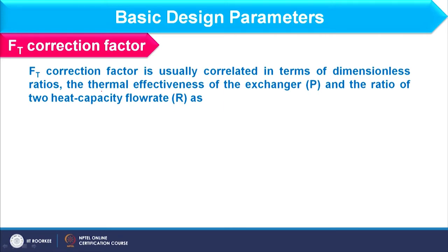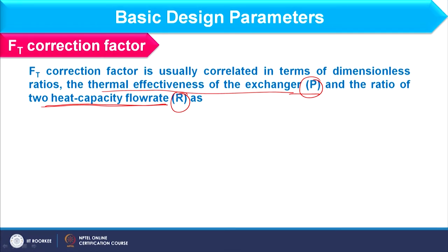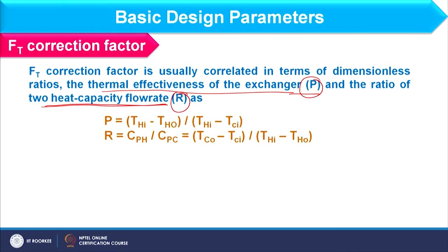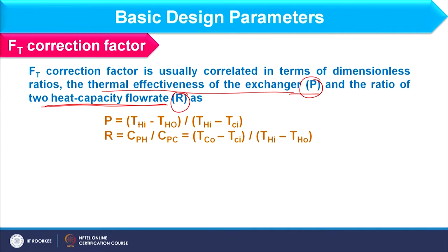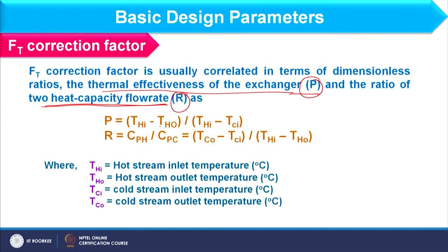As far as the FT correction factor is concerned, we consider two different parameters: the thermal effectiveness of the exchanger, represented as P, and the ratio of two heat capacity flow rates, R. Depending on these two values we determine the FT factor. P is the thermal effectiveness of the exchanger — how effectively heat transfer takes place. Its expression is P = (T_HI − T_HO) / (T_HI − T_CI).